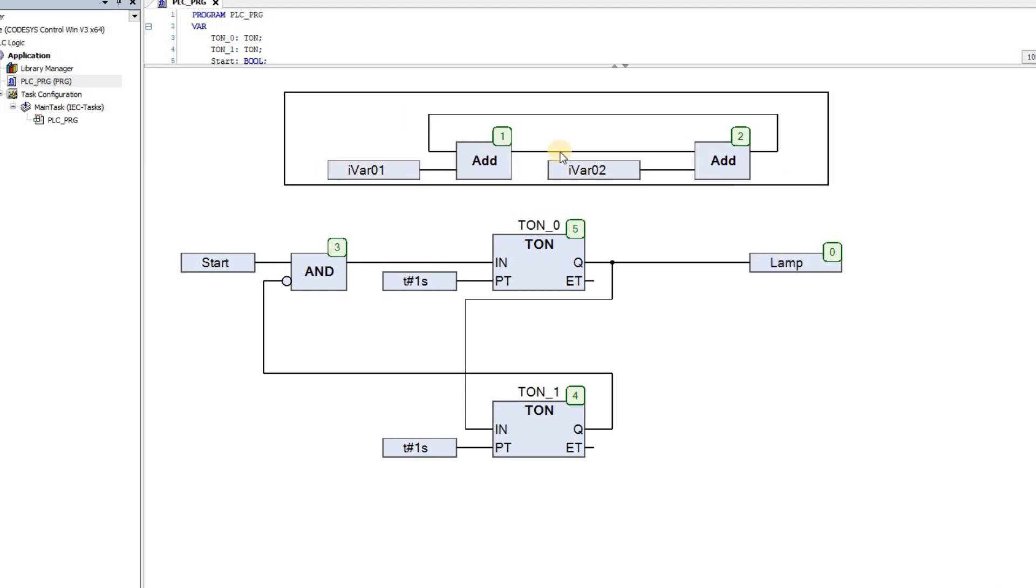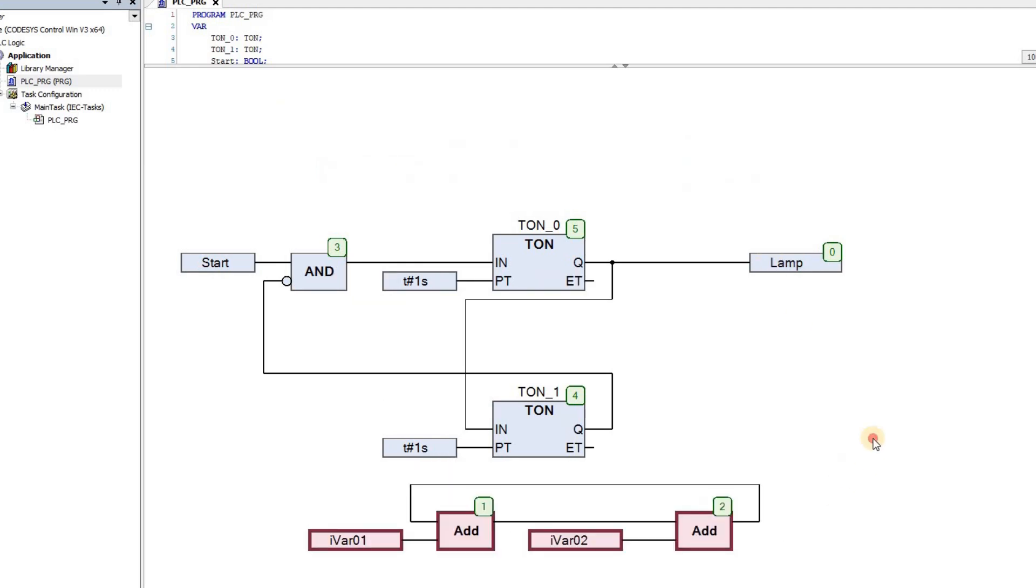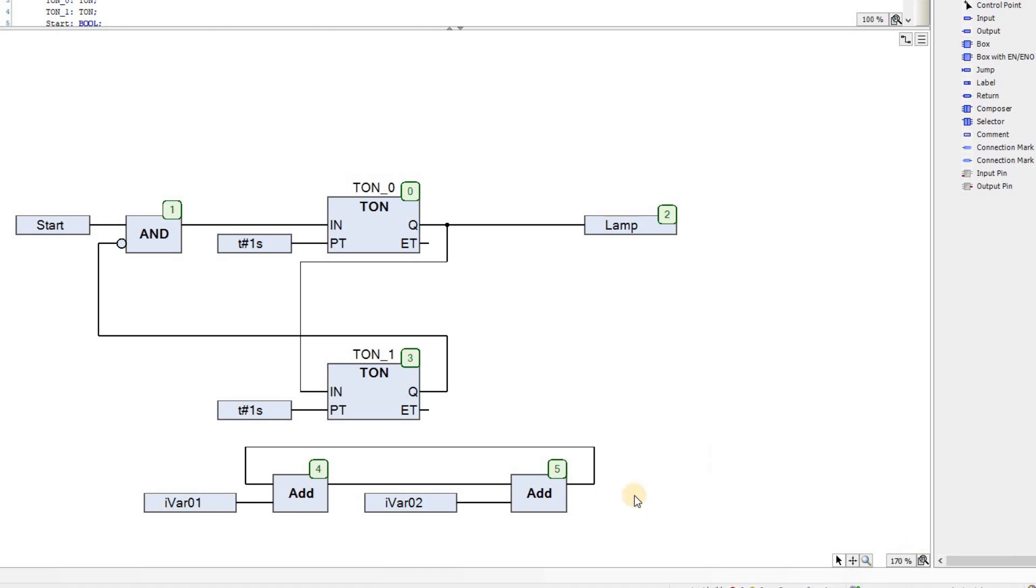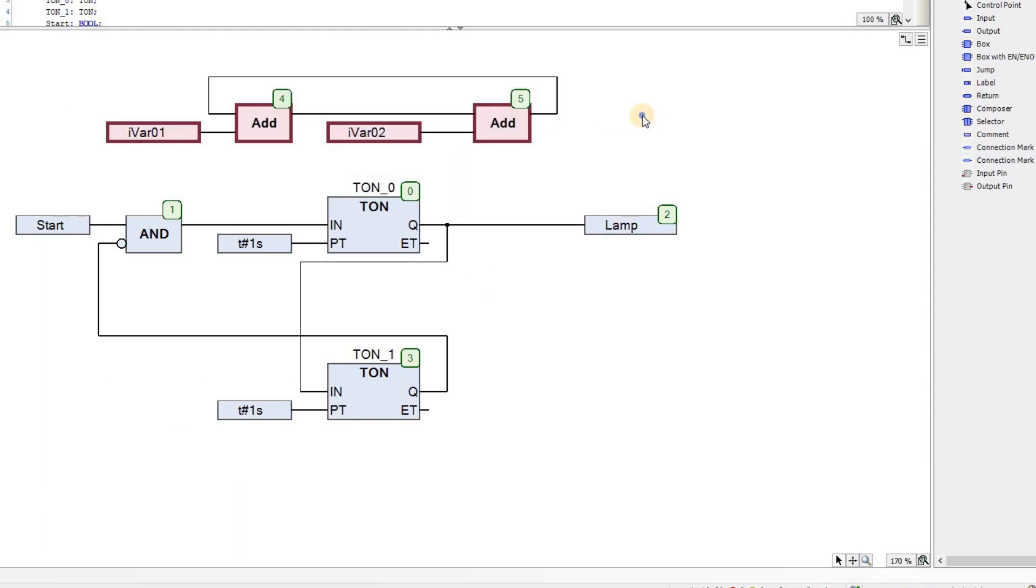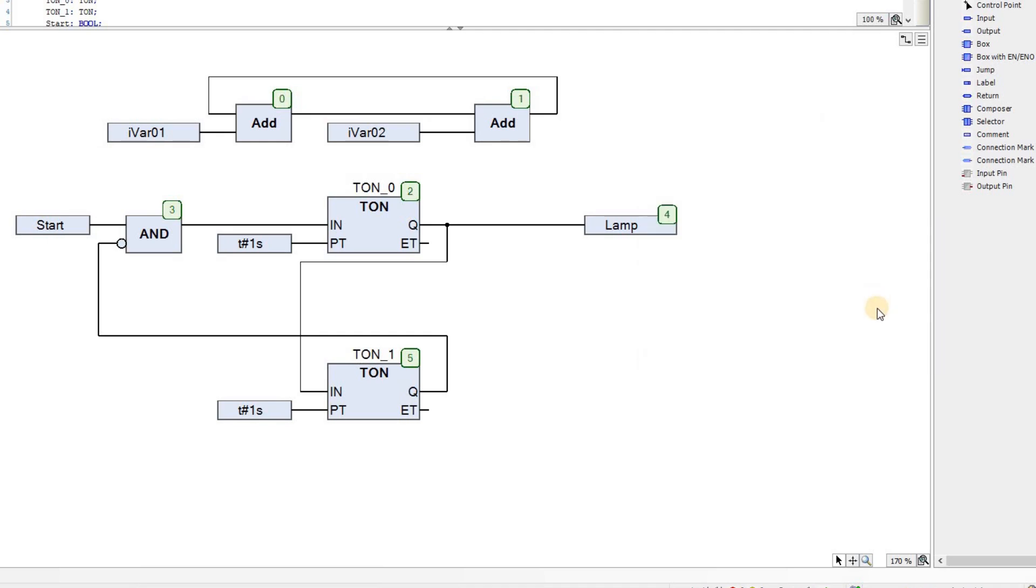If I want to get the execution order updated, I can right-click here again in the execution order, choose Order by Dataflow. When I do that, you see that this network will be executed first, and then the second network will be executed. So we have that option of updating the execution order according to the Dataflow whenever needed. In this mode, if you select any block and right-click on it, in the execution order, there are several options to choose.